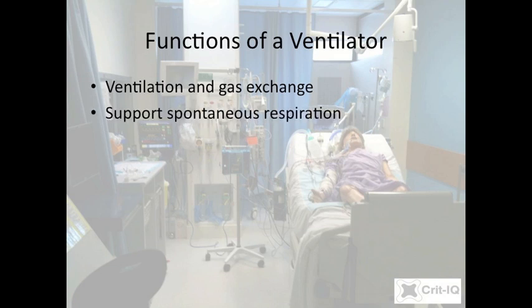Secondly, when the patient can breathe but not sufficiently so, a good ventilator can support the normal breathing of the patient. This ventilatory support, largely in the form of positive pressure applied when the patient initiates a breath, can assist transition from full mechanical ventilation to independent respiration. Thirdly, the ventilator should avoid inflicting any harm upon the patient. Good ventilators and ventilation strategies aim to reduce the potential complications.